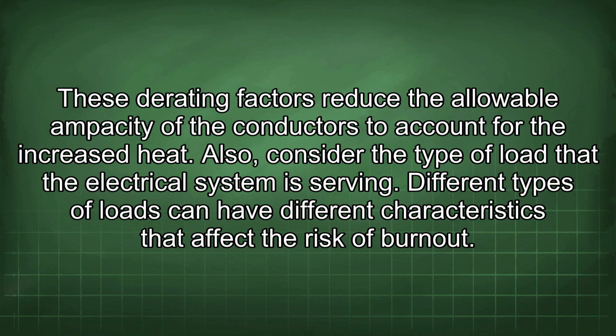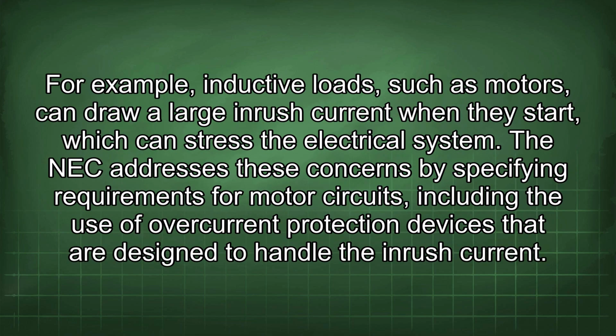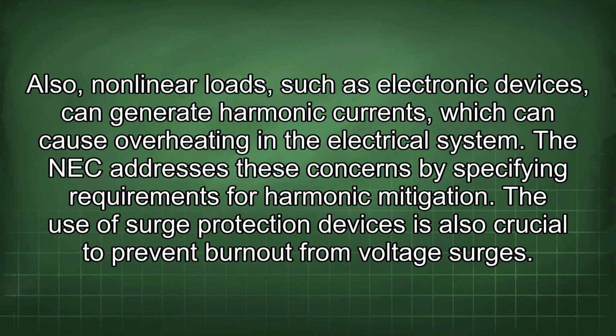Also, consider the type of load that the electrical system is serving. Different types of loads can have different characteristics that affect the risk of burnout. For example, inductive loads, such as motors, can draw a large inrush current when they start, which can stress the electrical system. The NEC addresses these concerns by specifying requirements for motor circuits, including the use of overcurrent protection devices that are designed to handle the inrush current. Also, nonlinear loads, such as electronic devices, can generate harmonic currents, which can cause overheating in the electrical system. The NEC addresses these concerns by specifying requirements for harmonic mitigation.